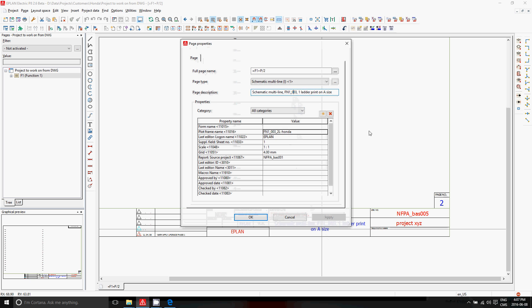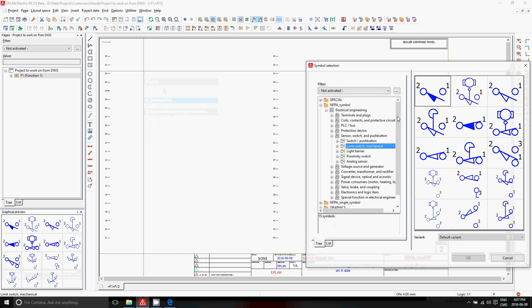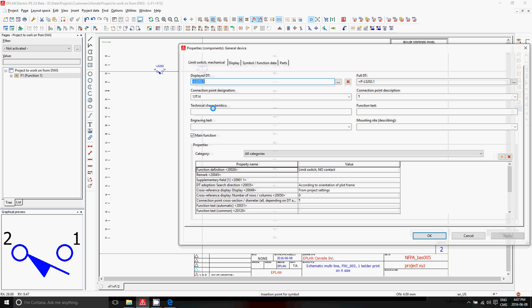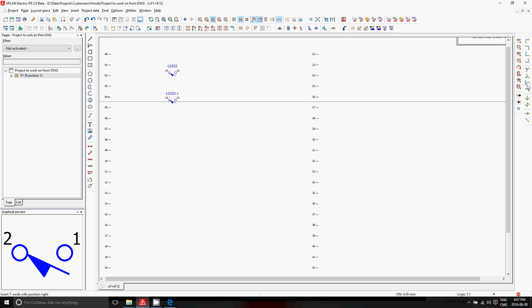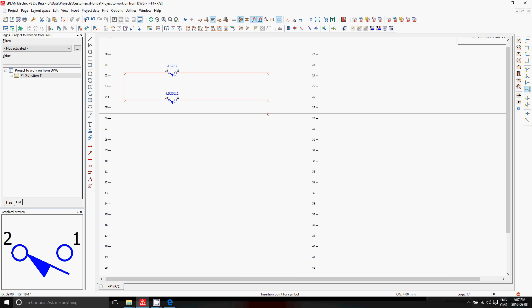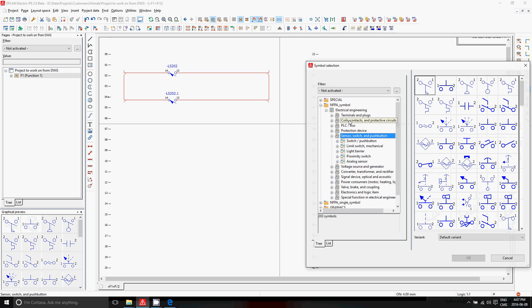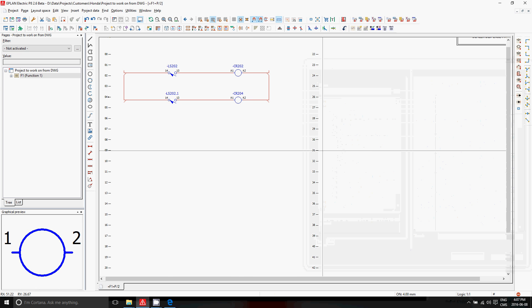When you're finished, you close it and you can actually use it. You can see the schematic description, which is the page description, fits right in that field. So I have my plot frame, and this plot frame now I can actually fill with regular symbols. As I fill them with regular symbols, it reacts like usual ePlan with auto-connecting lines. These auto-connecting lines are very interesting because they save a lot of time when you do your schematics — you don't have to draw them, ePlan draws them. Also interesting: once you have some lines and you have to add some coils or contacts, these lines get trimmed and we have automatic cross-referencing.